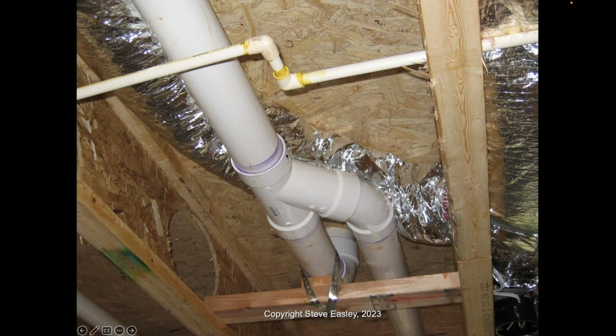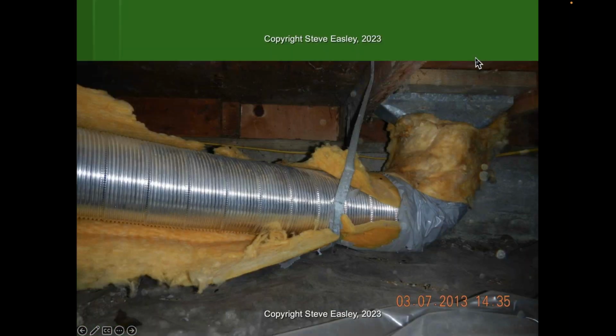Keep in mind that pre-planning is really, really important. Here, for example, plumber always wins. The ductwork was put in before the plumbing was installed, and therefore we get substantial compression. That's not going to be able to deliver adequate airflow to the room. For proper supports, instead of a 1-inch hanger, this should probably be closer to 3 or 4. If you can, don't suspend your ductwork from the attic. In some places, code officials require that. I never understood why, but anyway, this is not what we want to try to recreate.